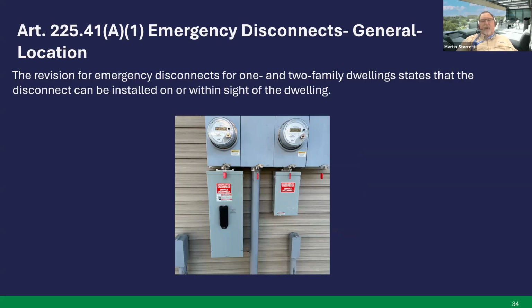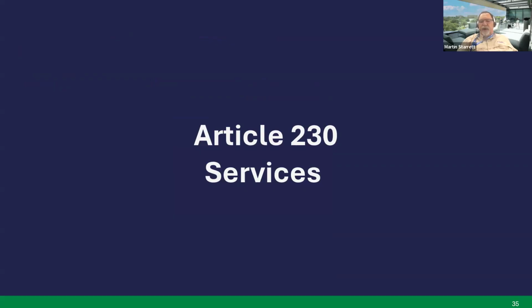So that kind of opens the door a little bit. Within sight of the dwelling means you can see it, not more than 50 foot. So if you have a disconnect where the conductors enter a structure or building, and I can see that disconnect, not more than 50 foot, then it could be used as an emergency disconnect, but it does not have to be on the dwelling. That's good. I'm glad they made that change. Opens the door for some more installation options. Article 230, services.